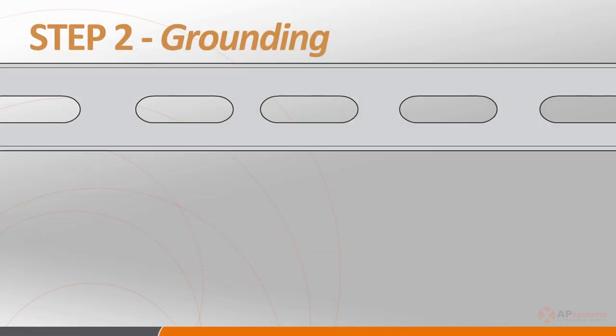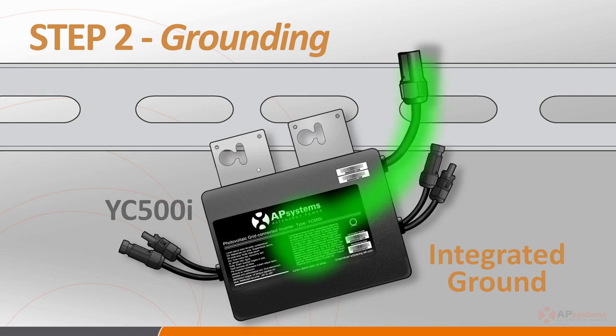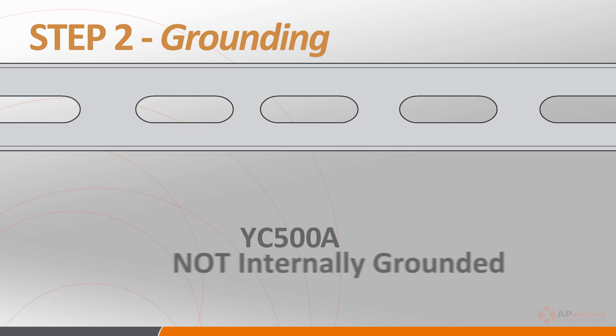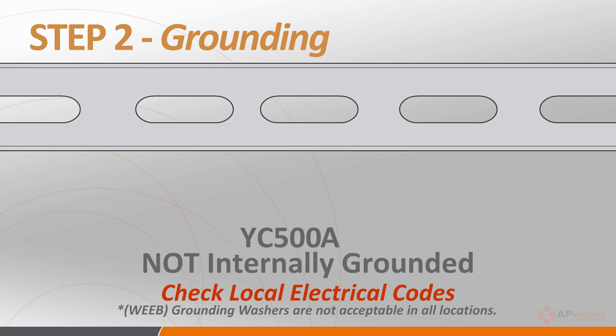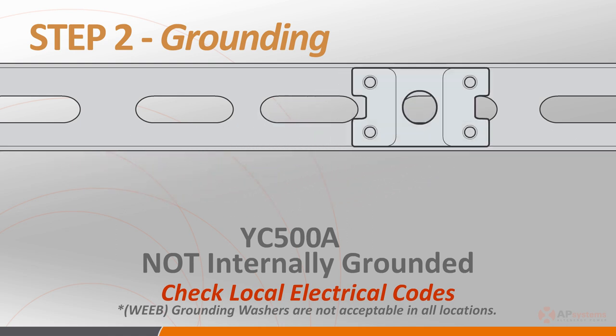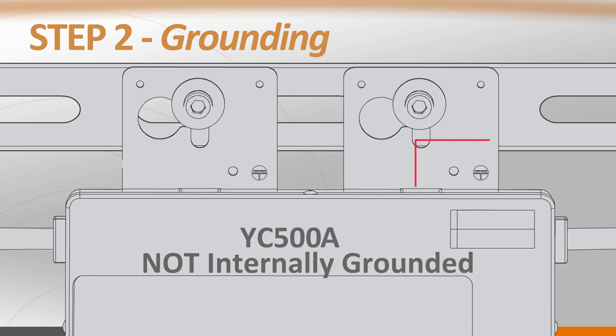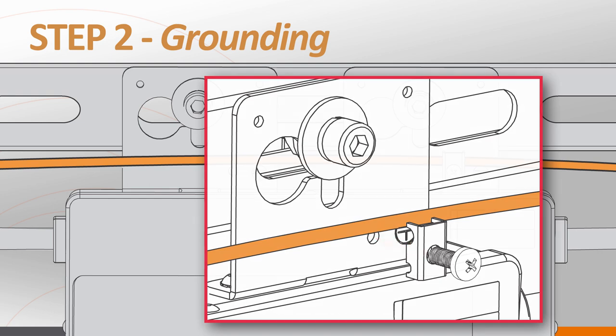Step 2 is making sure that the inverters are properly grounded throughout the system. Unlike the YC500I, which has a grounding wire integrated into the cable, the YC500A is not internally grounded within the chassis, so it requires an external ground. Depending on your jurisdiction — and it's always best to check with your local inspector — you can either use a grounding washer when attaching the inverter to the rail of a well-grounded racking system, or use the grounding lug on the YC500 to string bare copper wire to an appropriate system grounding location.